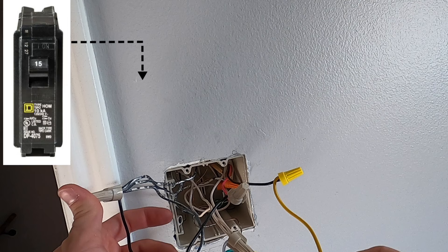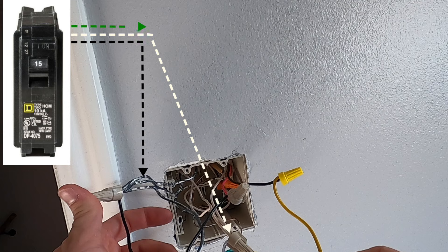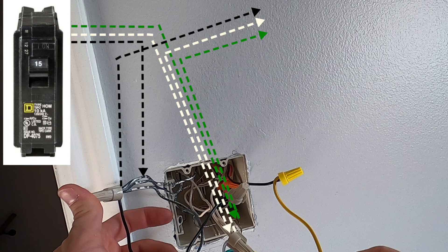So we have power coming from the circuit breaker into my light switch box. The white neutral wire coming from the circuit breaker connects to all my other neutral wires. And the bare copper wire connects to all my other green or bare copper ground wires. I also have another 14-2 wire set connecting to another switch box in the house. These wires are connected to the same. Black to black, white to white, and green to ground.